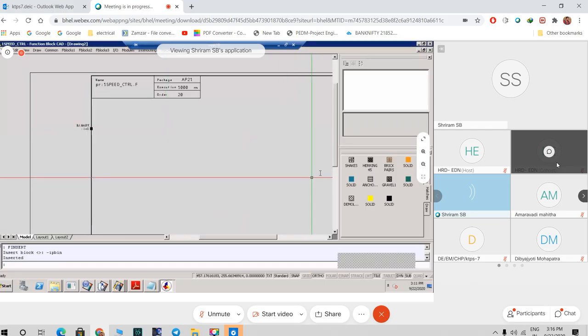Okay, one more thing. Package name and process area name need not be the same. That is actually not a requirement of Metso. I have just put it here for a sample. But it is recommended that you arrange it in a correct group. That is AP21. You can put it in AP21, because I have not exactly counted here, so I have put it in BP. But in your logics or at your site, wherever you are using, AP21 logics will be put under the AP21 folder only, so that you will be able to easily identify which package is for AP21.